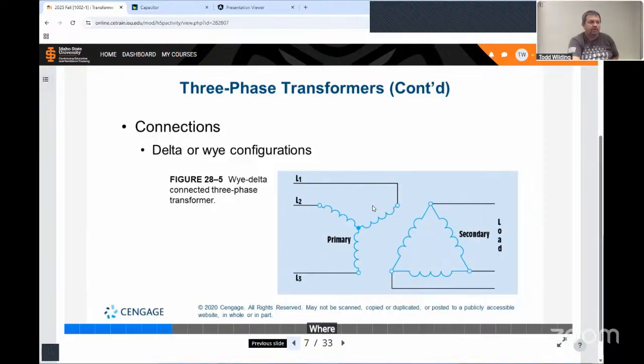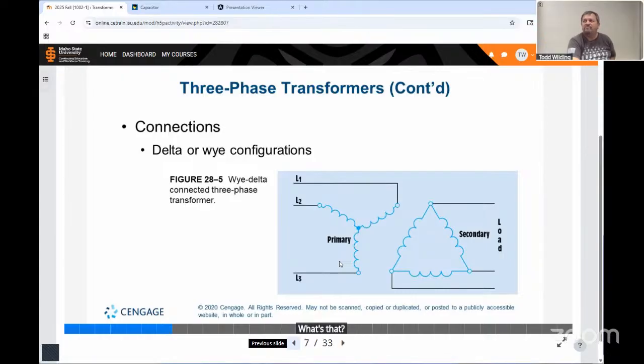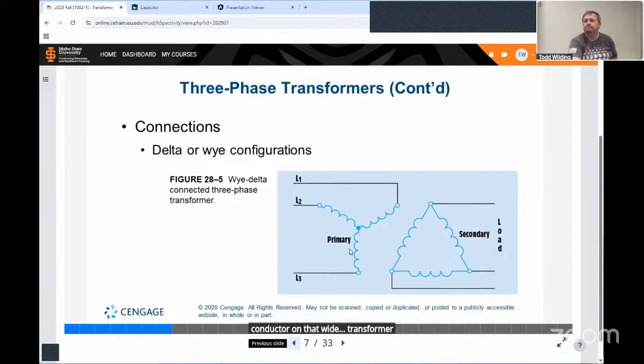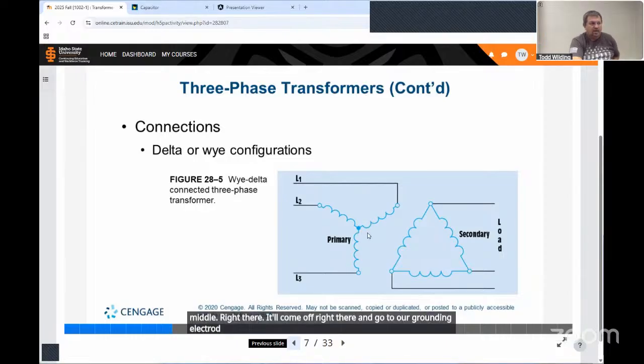Where would the neutral point be on the Y system? Where would I derive my neutral or grounded conductor on that Y transformer? Middle. Right there. It'll come off right there and go to our grounding electrode system. And that's where we're going to bond everything right there, except we do not do it on the primary, we do it on the secondary side.